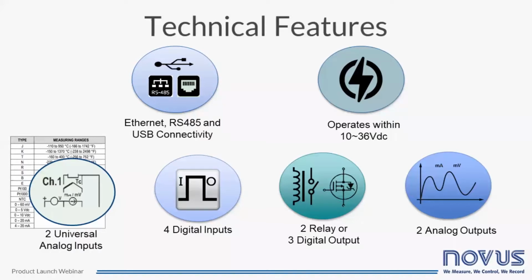The analog inputs are not electrically isolated from each other, but are isolated from the other DigiRail Connect circuits. Besides that, it has four digital inputs. These digital channels are suitable for receiving dry contact, NPN and PNP electrical signals. The maximum detected frequency is 250 Hertz for NPN or PNP type and 10 Hertz for dry contact.